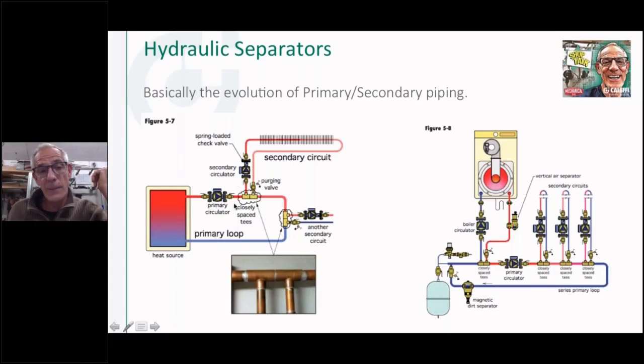And by putting this little separation, these closely spaced T's with zero pressure drop between them, I isolate, hydraulically speaking, these pumps from one another. Now, obviously they're all in the same water. Some people say, well, is that a heat exchanger in there? Do you have two different fluids going on here? No, there's nothing inside there. It's just the space between there that's creating this separation, this low pressure drop separation device, which we call closely spaced T's, and that's what makes it primary secondary.